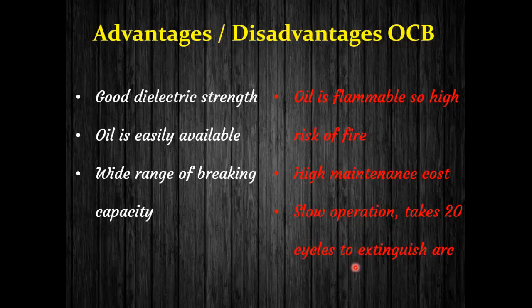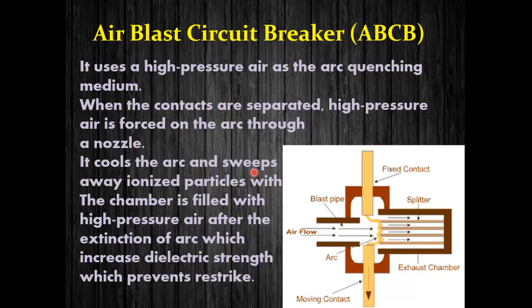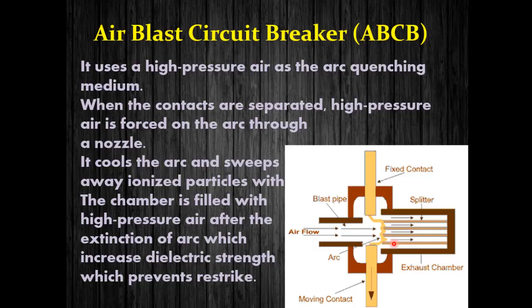The air blast circuit breaker (ABCB) uses high pressure air as the arc quenching medium. When the contacts are separated, high pressure air is forced into the arc, which pushes and elongates the arc into a splitter, helping to cool it. The high blast of air sweeps the ionized particles within the chamber. The chamber is then filled with high pressure air after arc extinction, which increases the dielectric strength and prevents restriking of the arc.